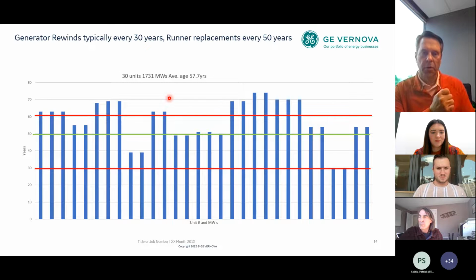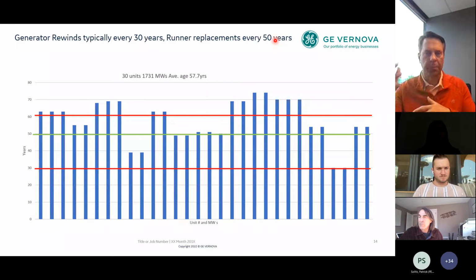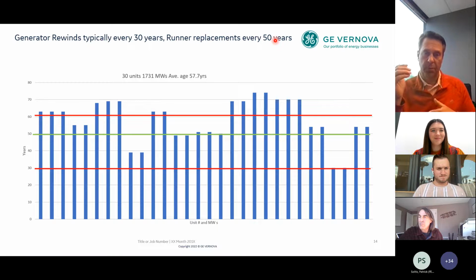Typically, when you're looking at a power plant with turbines and generators, the generators typically get rewound every 30 years or so, and runners are replaced every 50 years, plus or minus, but some things can last longer or wear out faster. We know they're wearing out faster because of the way they're being operated and cycled. For this particular customer, they have 30 units in their fleet, over 1,700 megawatts, and the average age is 57.7 years. This was a few years ago, so it's probably over 60 years now.